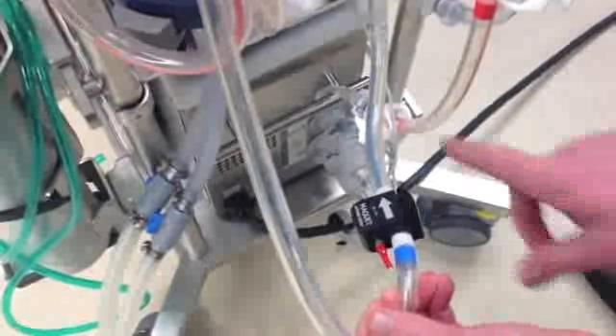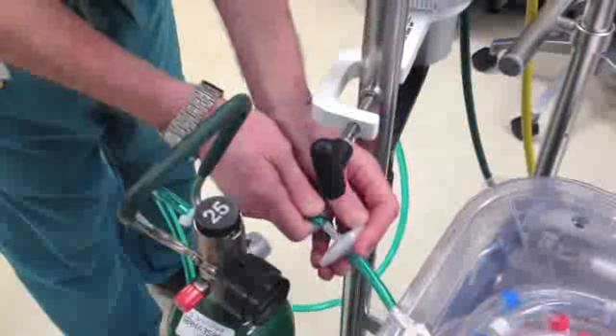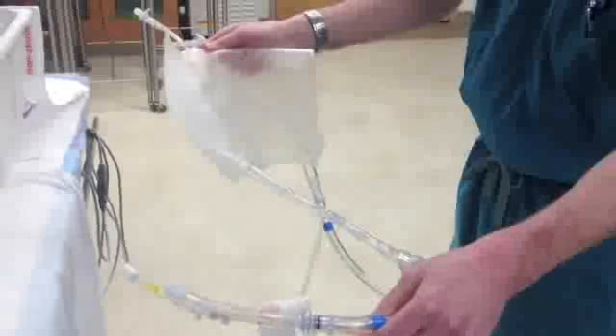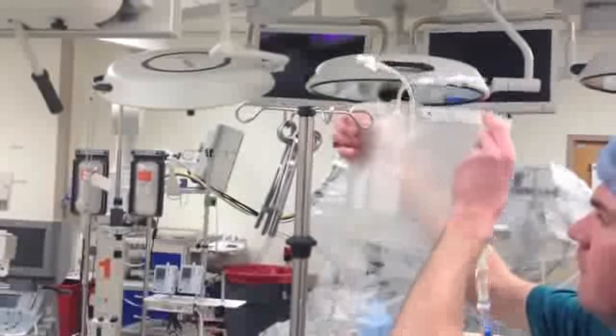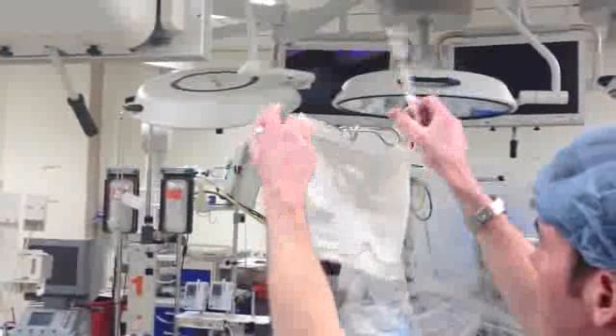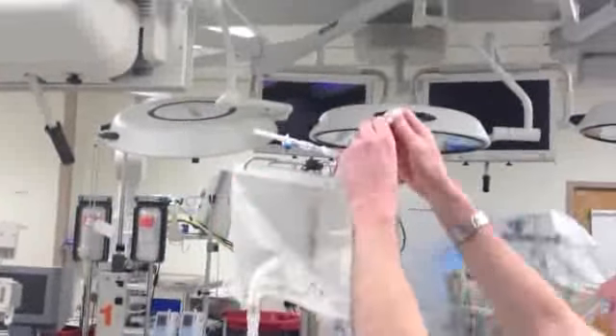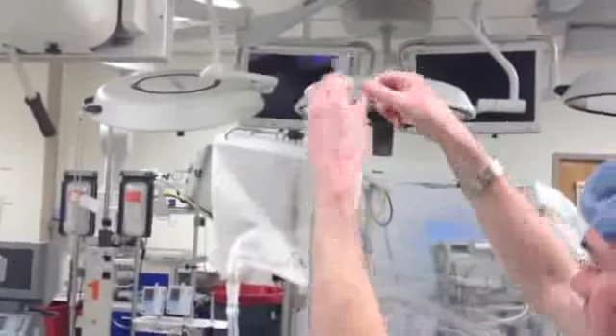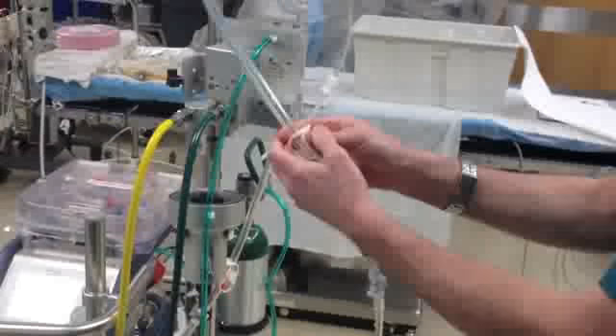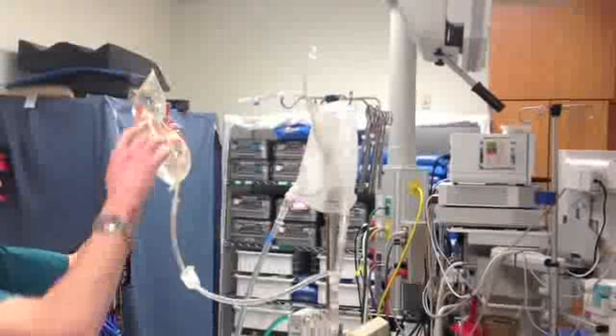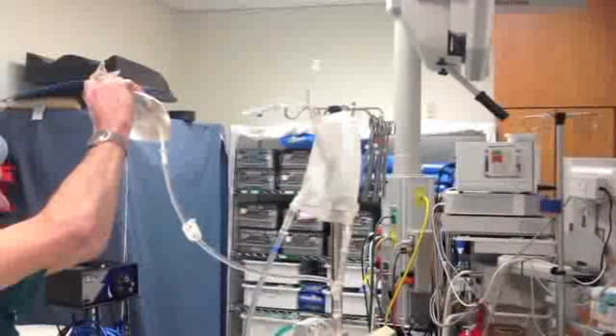Then we connect the flow probe to the blue line in between the 2 white pieces of tape, which will be on your set. Just put it in there and snap it closed, and make sure the arrow is in the direction toward the CardioHelp console, so the flow is going toward the console. You'll connect your green gas line, your oxygen line, and then you'll remove the priming bag from the disposables tray, and then you'll hang that onto the IV pole that's right there with the system, and you'll hang it open like this so that it can be filled, and you'll close the stopcocks up top, and then you'll clamp off the blue line, which will be used later to fill the circuit.